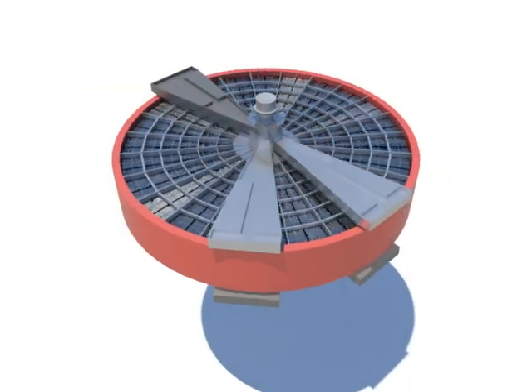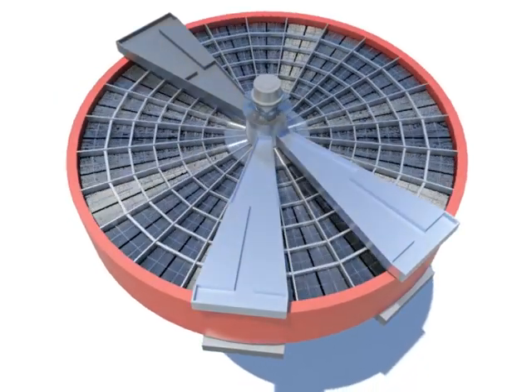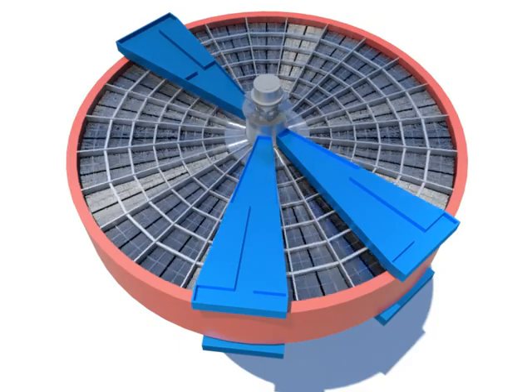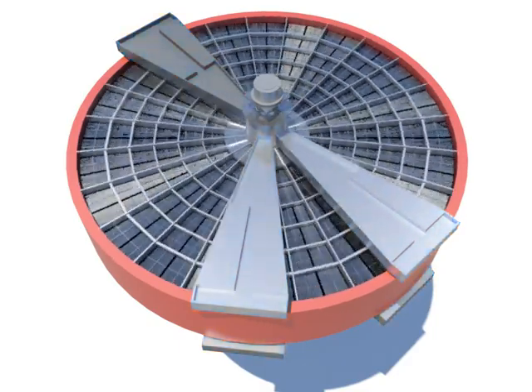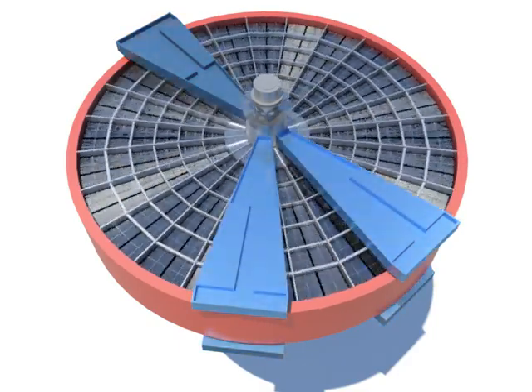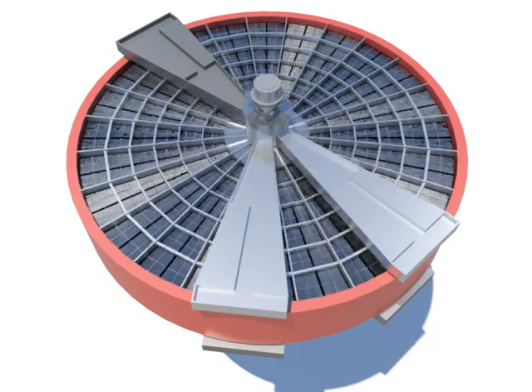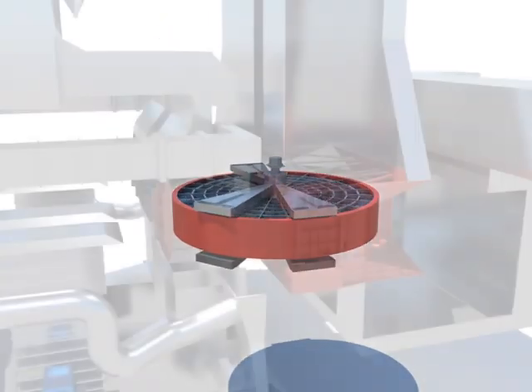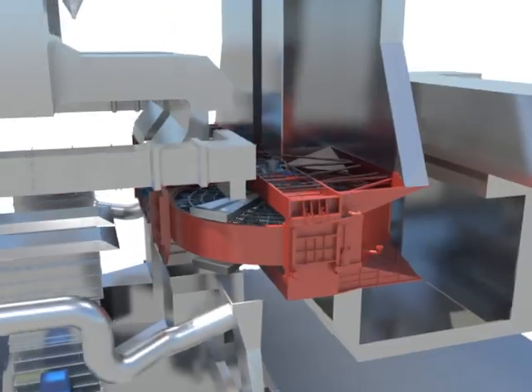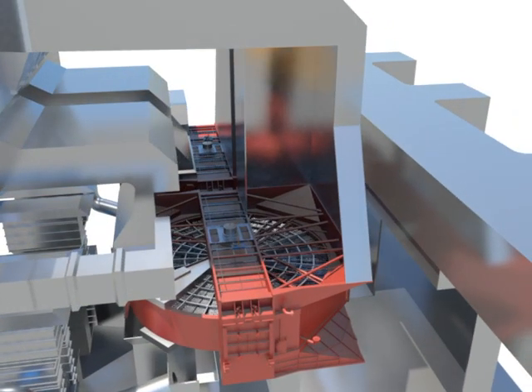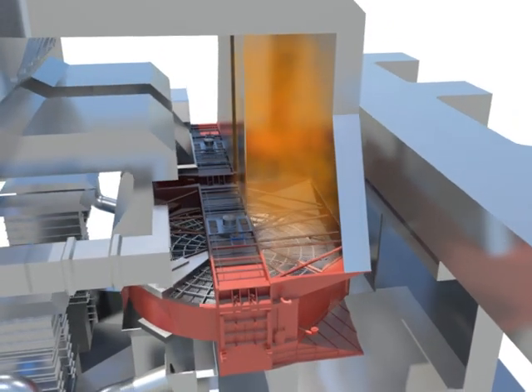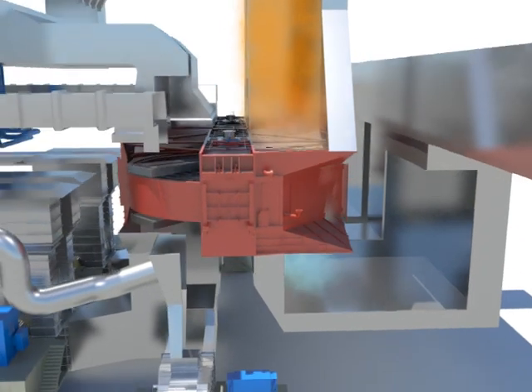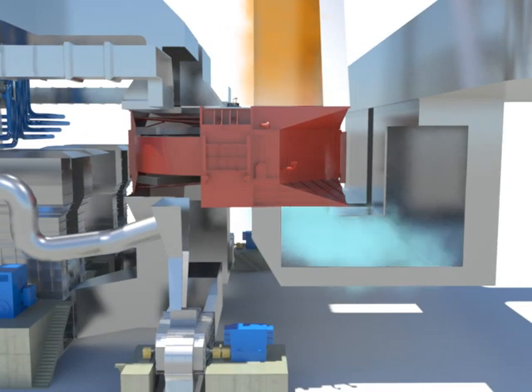The upper and bottom rotor are separated into a tri-sector, thus flue gas flows at one side and combustion air, coal conveyance, and drying air flow on the other side. In addition, the heating element plays a role as a heat supplier, transferring generated heat from the flue gas to combustion air, coal conveyance, and drying air.